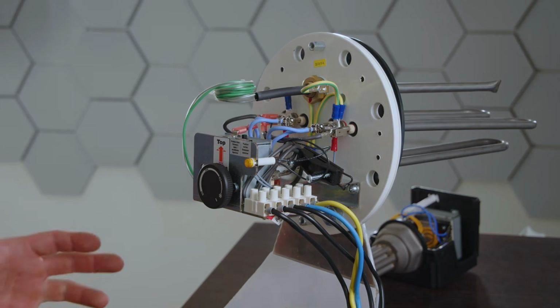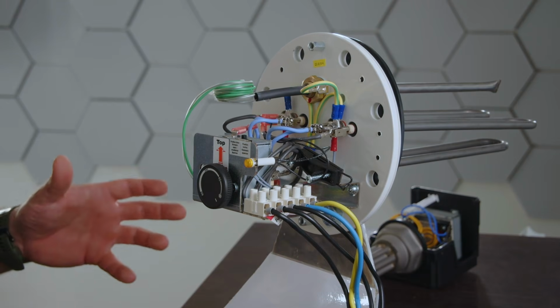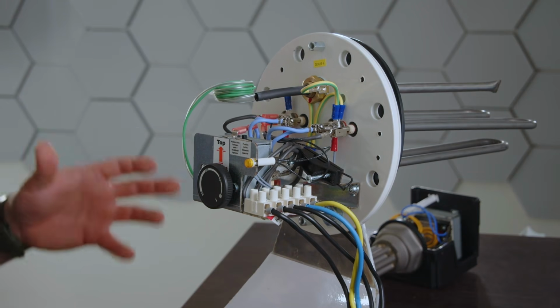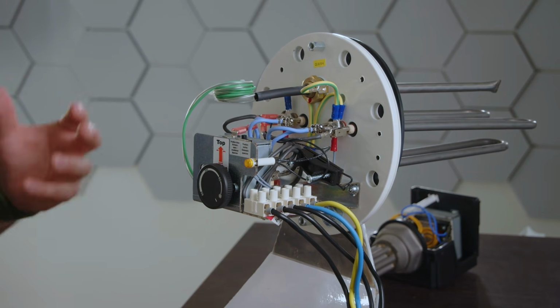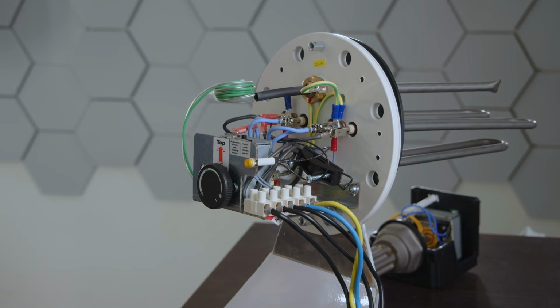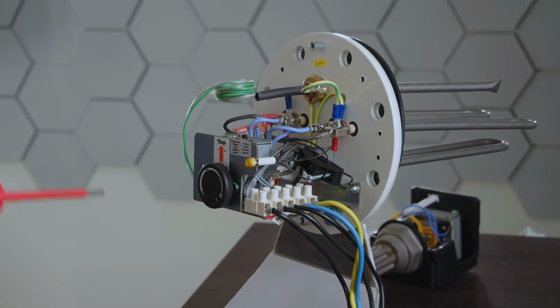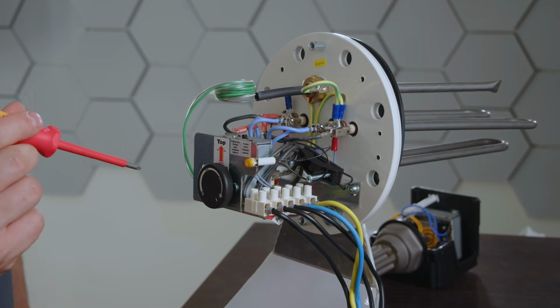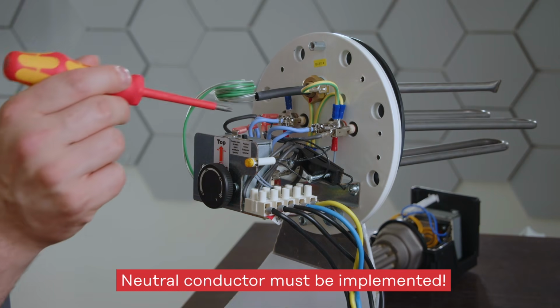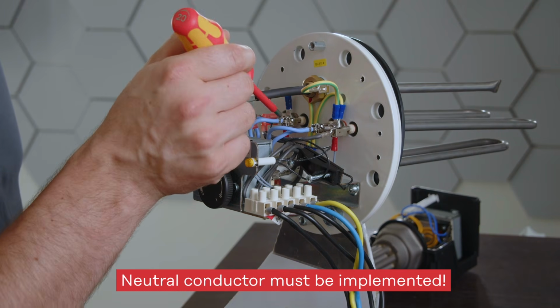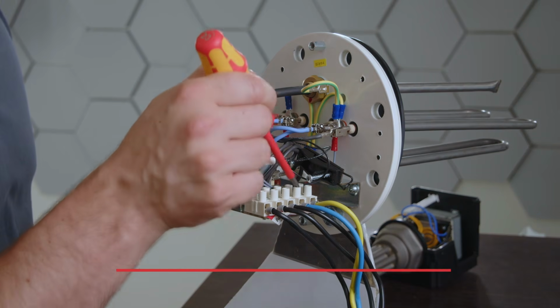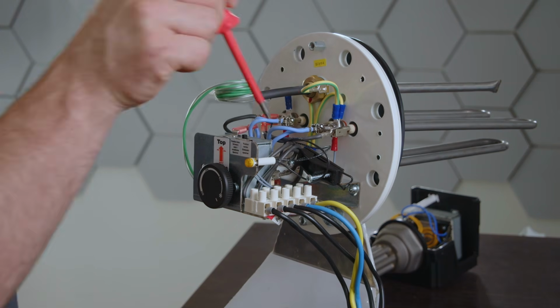First of all, we already have heard single phase 3 kilowatt and three phase 9 kilowatts. That's important to not exceed these limits, otherwise you will get an error message or you could even destroy the Ohmpilot. Next up, it's important that we have a star topology, a star wiring. So no delta or triangular connection here. And the second very important topic is to have also the neutral conductor carried out. So here we have a star connection and we see the neutral conductor is carried out and then led to our Ohmpilot.